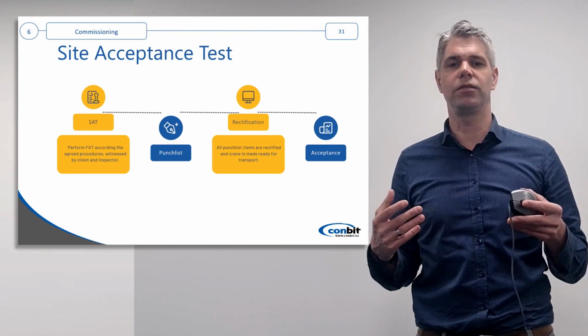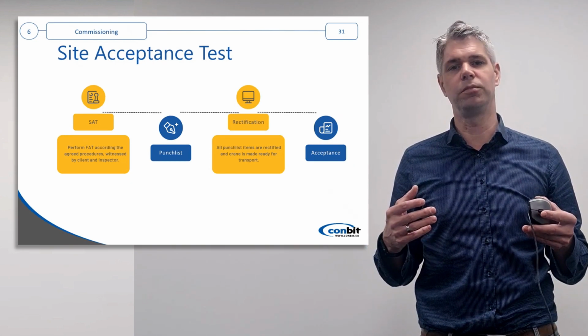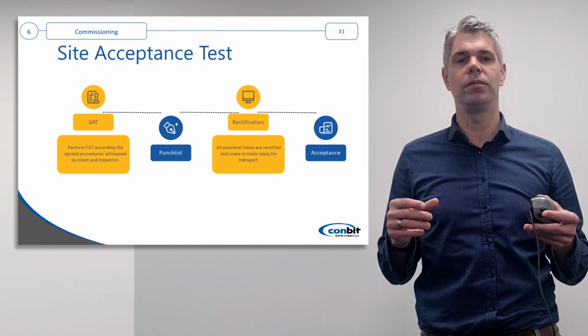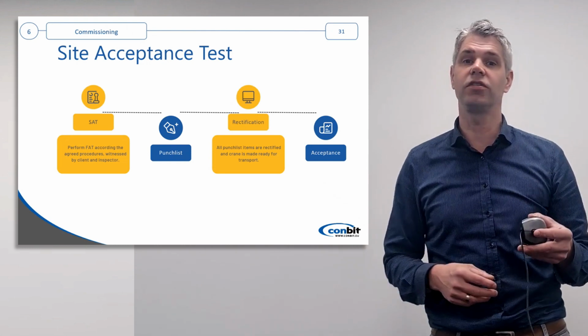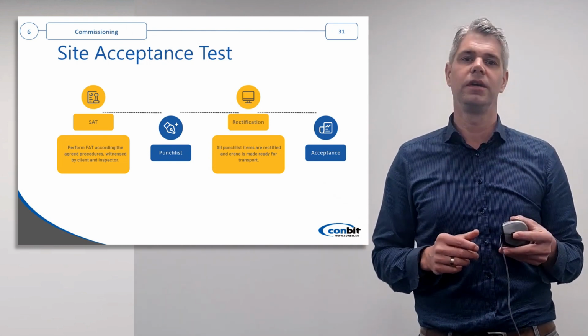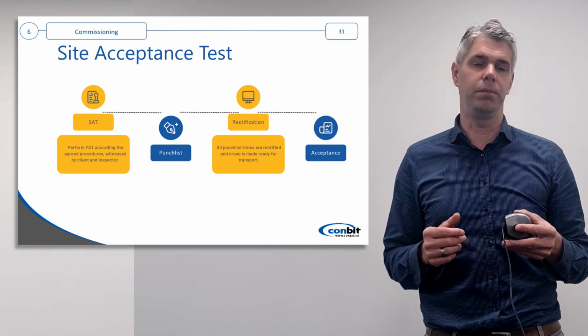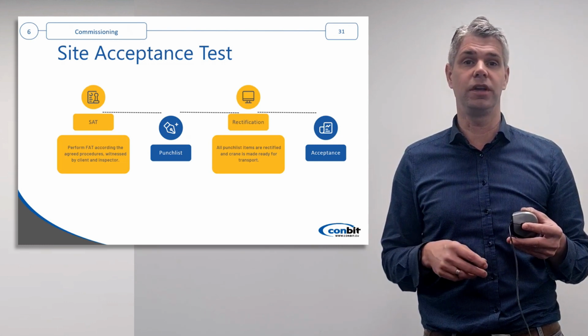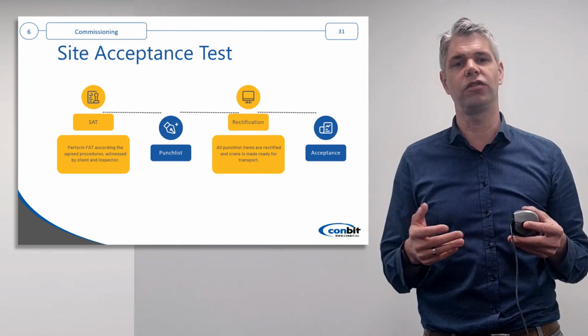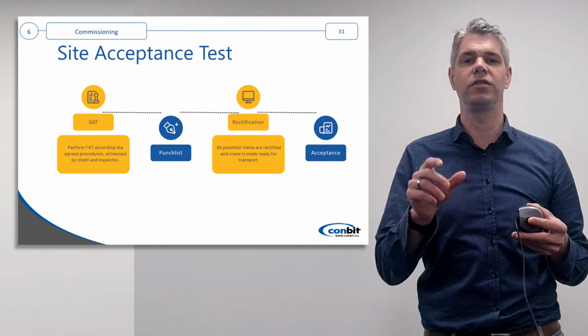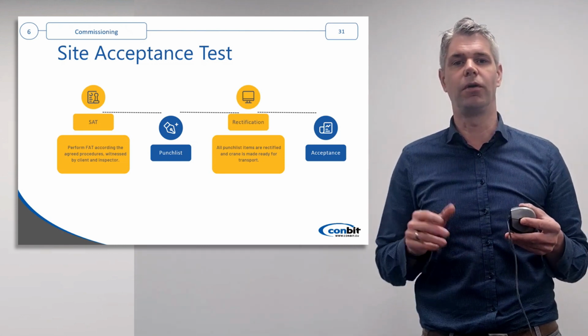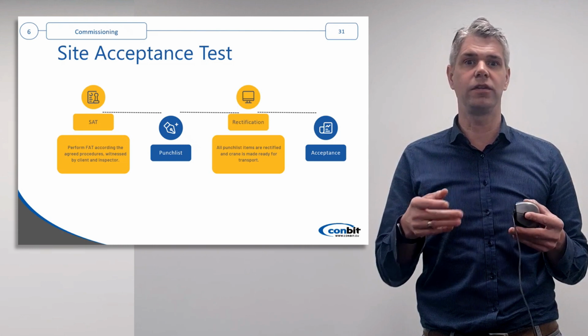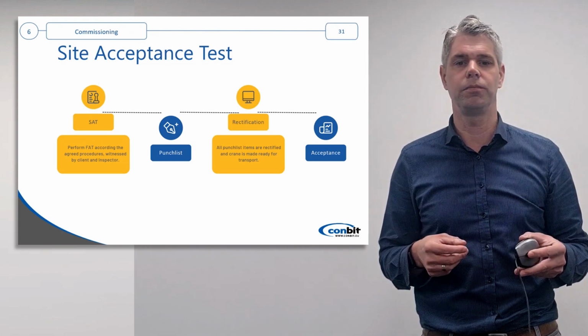Site acceptance test might have punch list items. Some of these punch list items are minor and can be rectified after the site acceptance test. Others you will need to do before you get your initial inspection certificate. And the initial inspection certificate is basically the handover document from the manufacturer or the contractor to the final user.